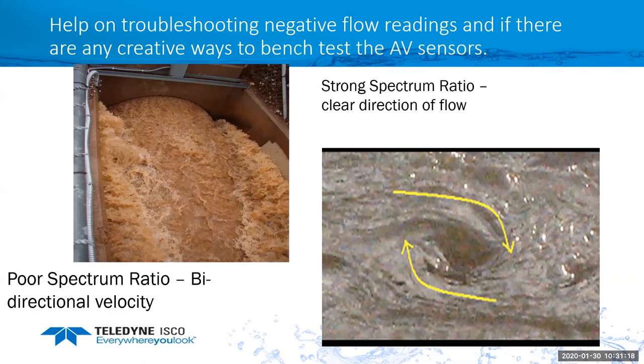If there's debris in front of the sensor, it could create that swirling, and that could be an indication you need to send somebody out there to clean that channel. So you can be proactive with this: if you see the ratios start to drop and your spectrum start lowering, send a technician out to clean it before it gets completely covered.